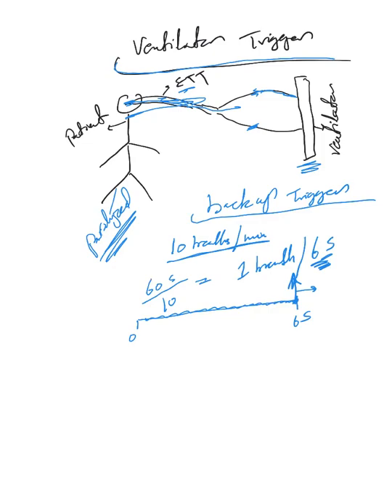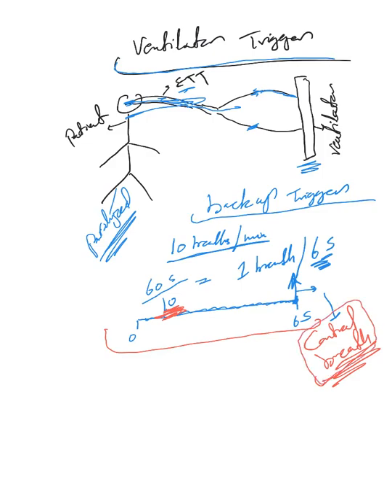This breath is triggered and delivered by the ventilator, and we call this kind of breath a control breath, because it was initiated and delivered by the ventilator. As you can see, this is mainly a backup mechanism, so this patient at minimum will get 10 breaths per minute.